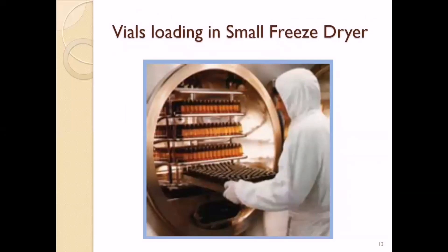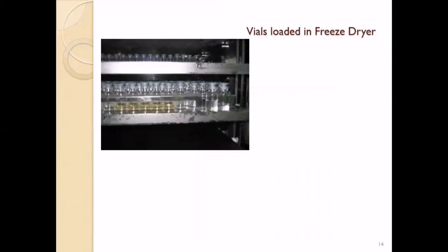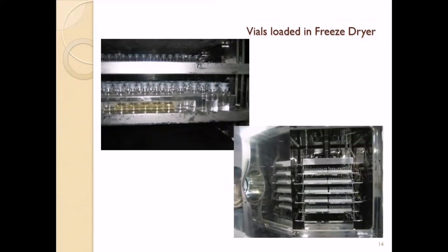In small lab-scale freeze-dryers, loading can be done manually where single vial trays are loaded by hand, as there is less concern about sterility or environmental conditions. In commercial scale, the process will be automatic under laminar airflow, since laminar airflow is needed to provide Grade A protection to the vials. Here we can see how vials look when loaded onto the shelf — half-stoppered with liquid product filled inside, not yet subjected to the freeze-drying process.